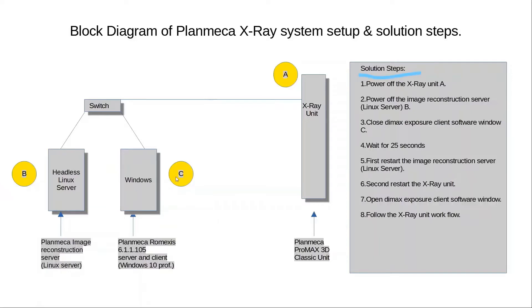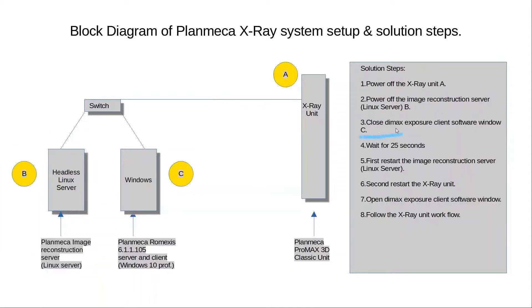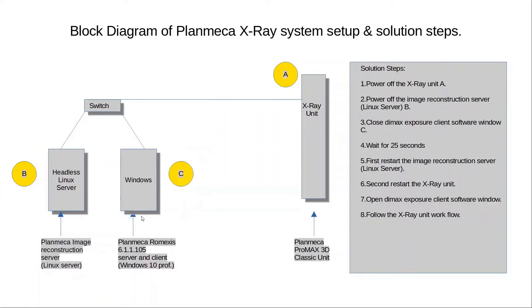With an understanding of the X-ray system setup block diagram, it will be easy to follow the solution steps. First, we need to power off the X-ray unit, represented by A. In the second step, we need to power off the image reconstruction server, represented by B. In the third step, we need to close the dimax exposure client software window, represented by C. Once that is done, move on to step 4, which is to wait for 25 seconds.